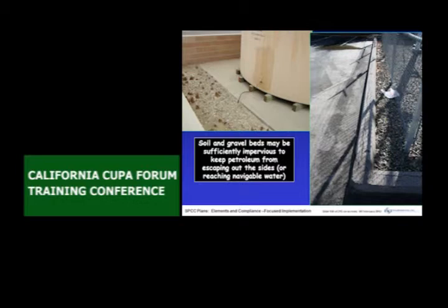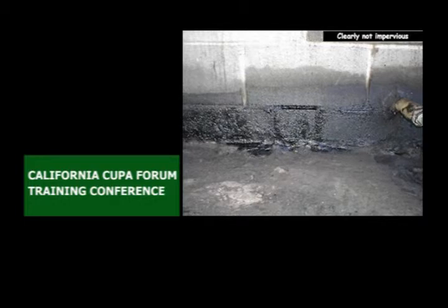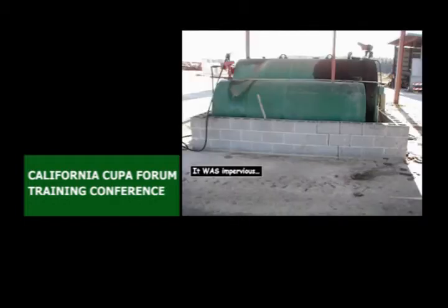This is for a substation? Yeah. Maybe they need to start working on this, but yeah, that's fine, general containment. It's going to soak right in, gravel bed. And then it goes into the ground. Waters of the state versus navigable waters. Different. This is not impervious. Right? This is not impervious. Used to be. Not so much.